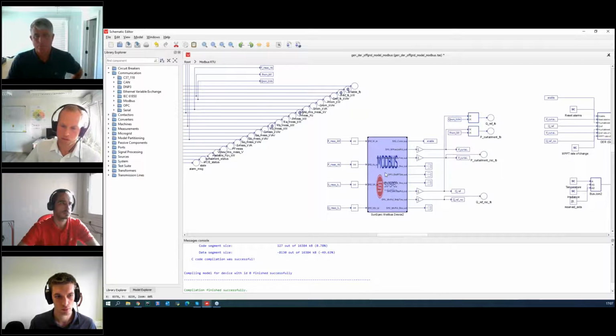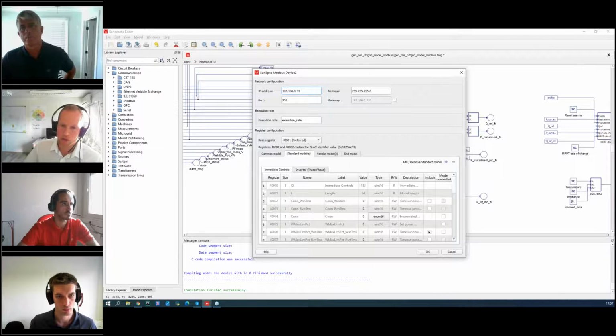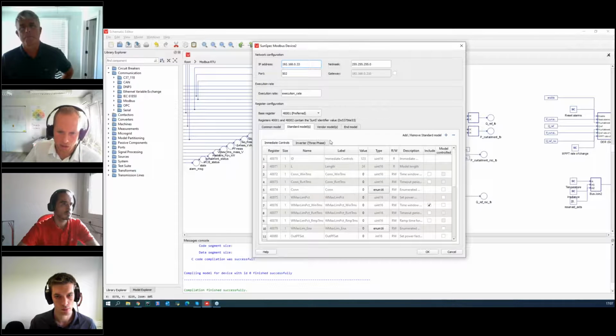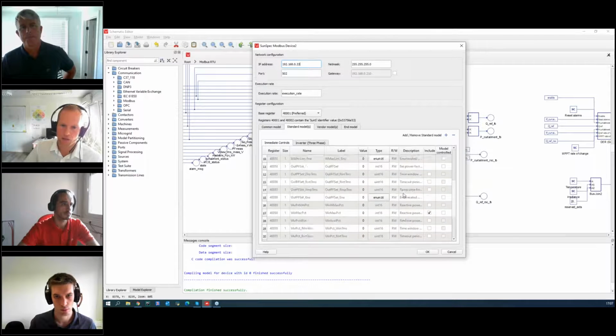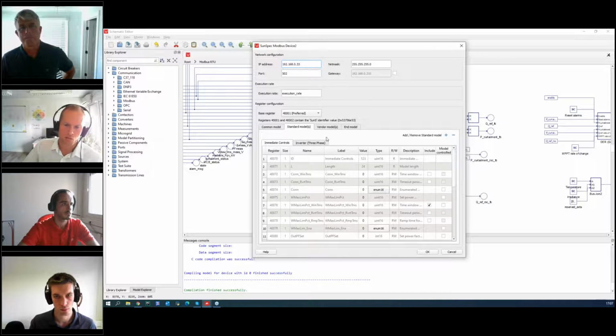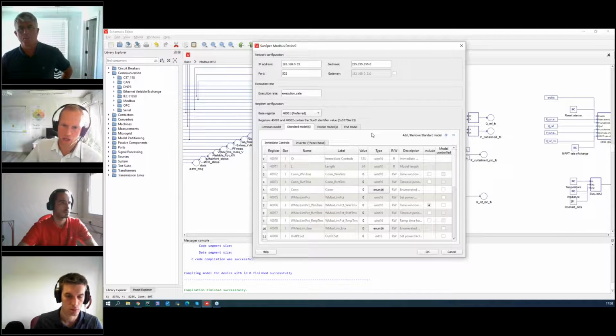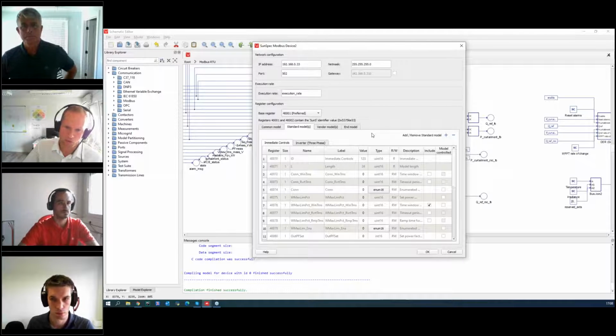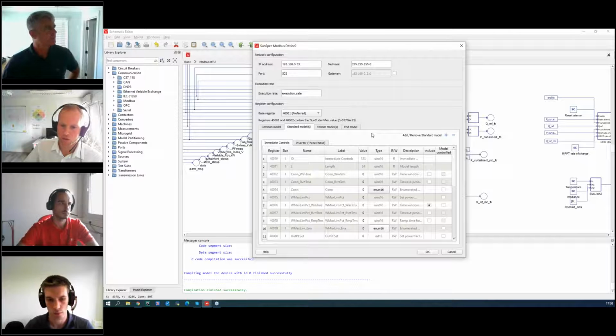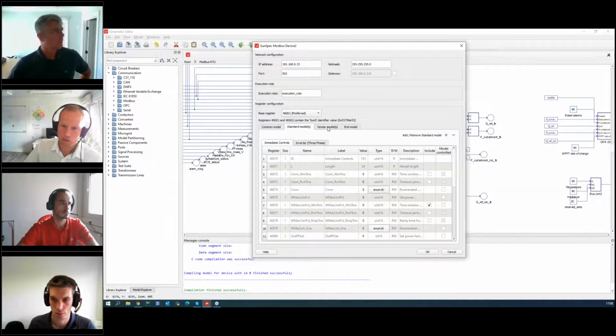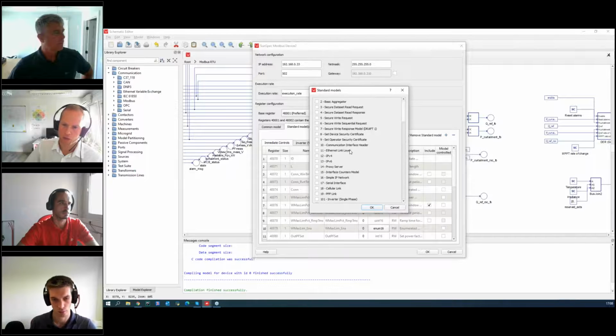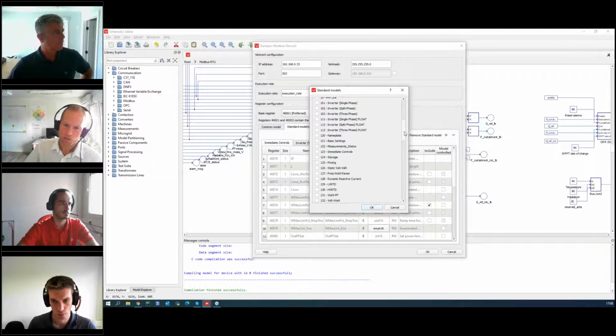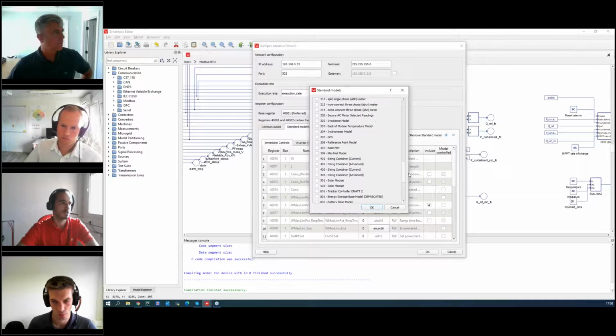So if we enter the solution already shown, we can add all these different register banks that are defined according to SunSpec. We can configure it the way we want, and we can even add standard models, common models, but also vendor-specific models, as we can see, can be added in a model. So in that regard, we can configure it in any way necessary to emulate just any Modbus SunSpec compliant device that we might use. So a lot of options here.